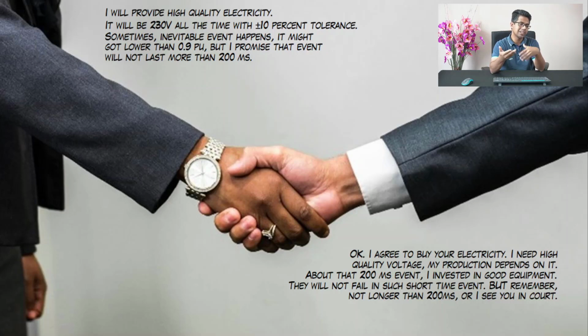Okay, and the customer side agree with that. Okay, that means the customer needs to install loads in the site that can handle this 200 millisecond below 0.9 pu. Okay, we will talk about this more about what's the agreement. Okay, there are some standards that need to be abided by both parties.